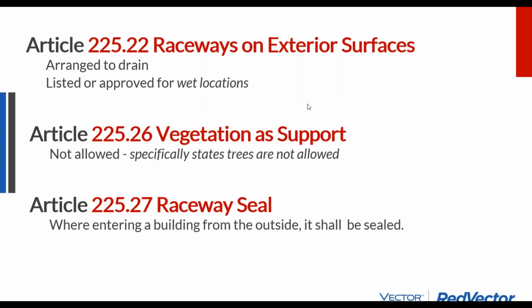Raceways need to be arranged to drain. Sometimes, when I first got into electrical, I'd look at power lines forming drip loops before they go into the house, and I'd say, man, why do they make it look so ratty, having these power lines just make these droops before going in? Well, it's so that the rainwater will fall down the line and drip off the conductors. And that applies not just to the power lines going into your building, but also to solar conductors coming off the array and into the box before they go down into the roof, or solar conductors coming down the wall before they go into the next piece of equipment.